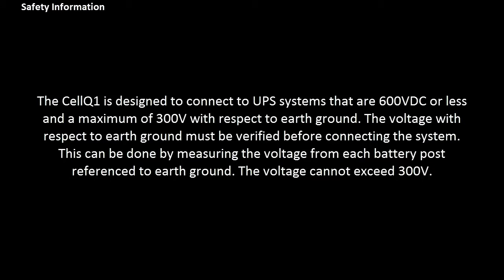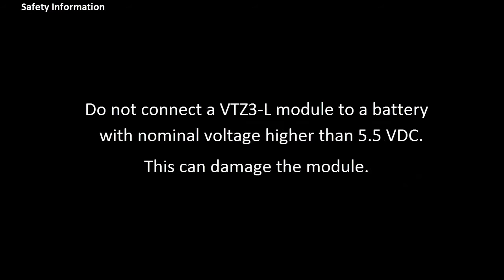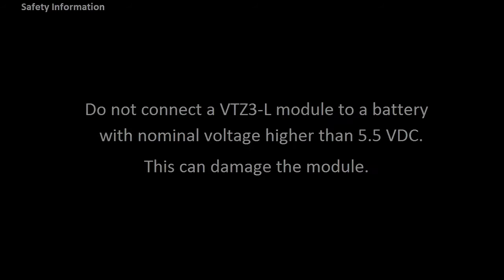The CellQ1 is designed to connect to UPS systems that are 600 volts DC or less and a maximum of 300 volts with respect to earth ground. The voltage with respect to earth ground must be verified before connecting the system. This can be done by measuring the voltage from each battery post referenced to earth ground. The voltage cannot exceed 300 volts. Do not connect a VTZ3-L module to a battery with nominal voltage higher than 5.5 volts DC. This can damage the module.